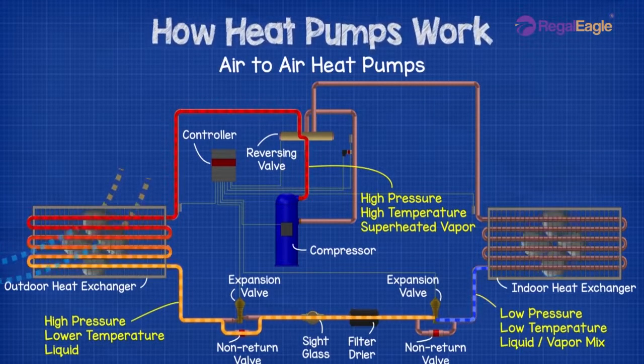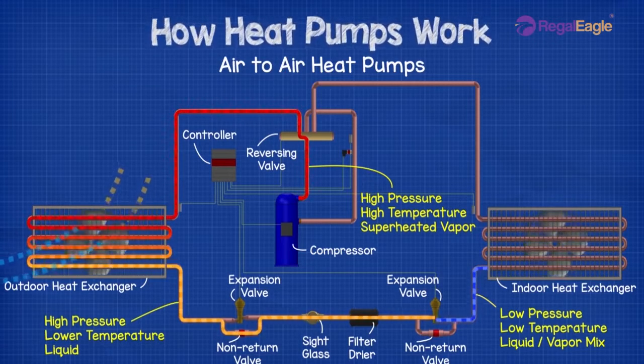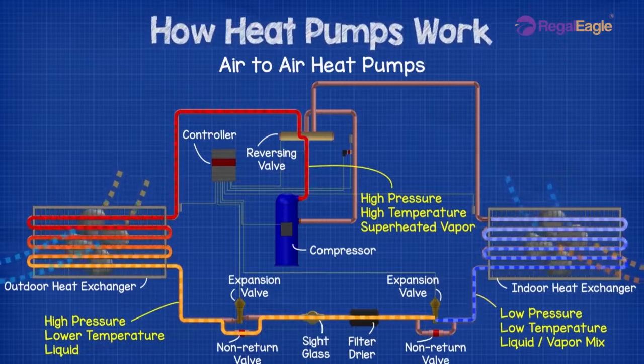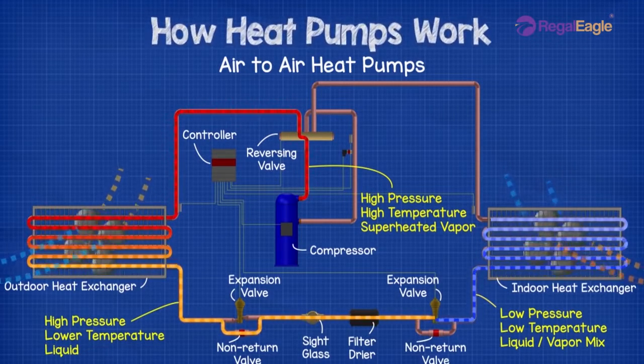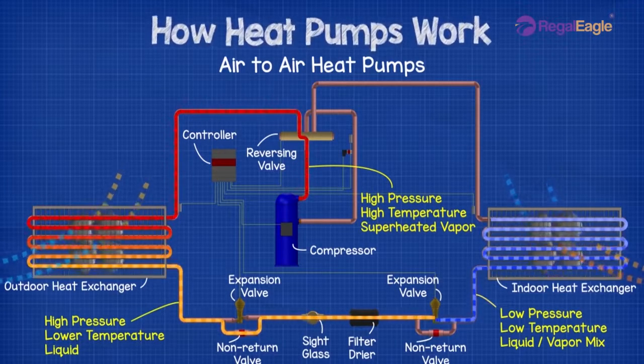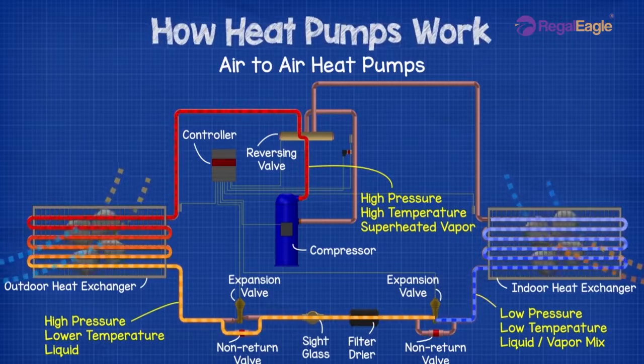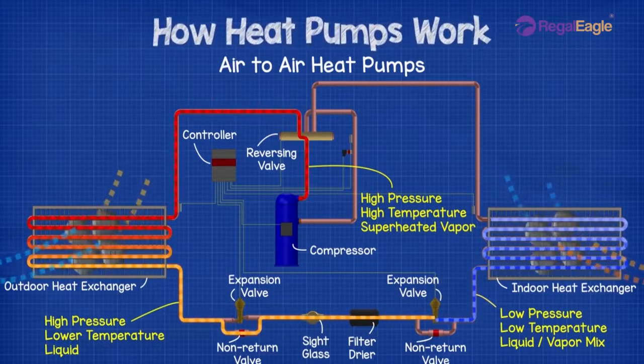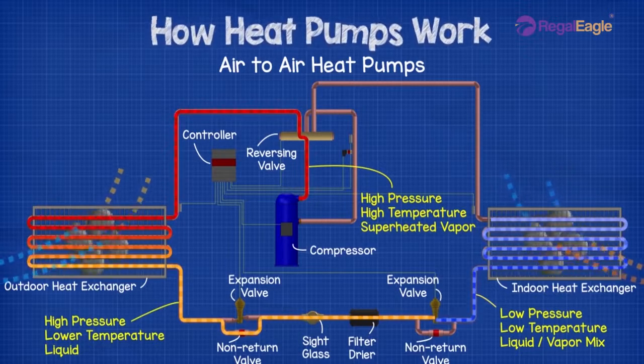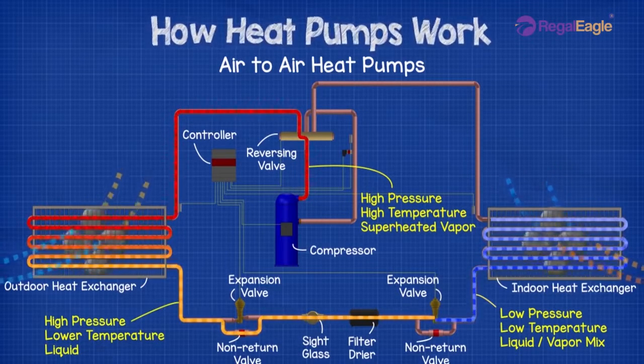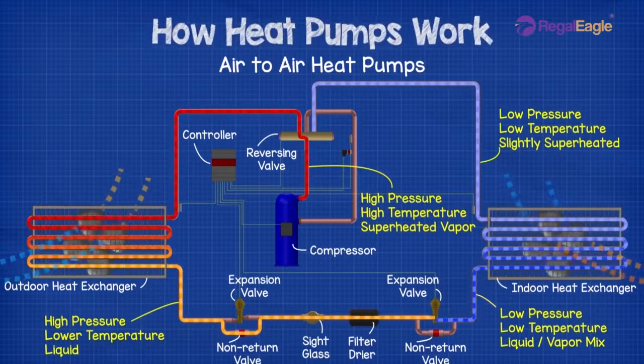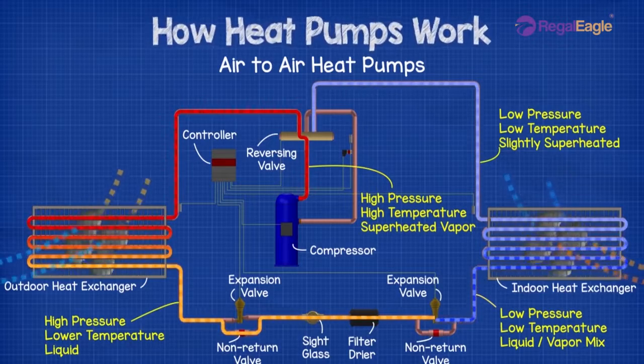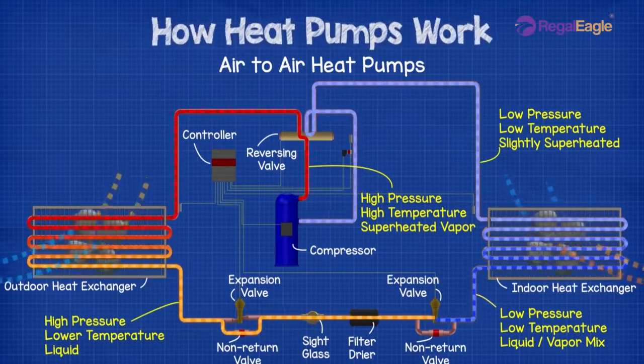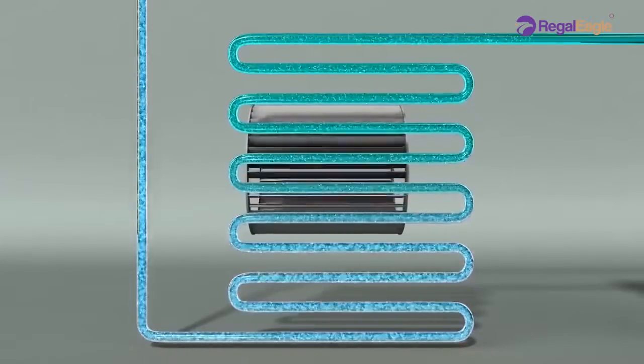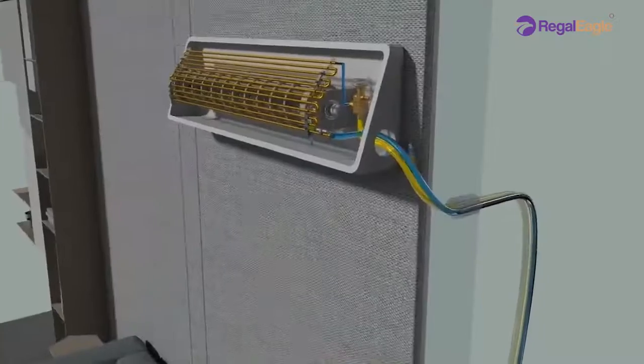It then flows into the indoor heat exchanger, where the fan blows the warm indoor air over the coil, which causes the refrigerant to absorb heat from the air. The air that lost heat becomes cooler, and a cooler breeze comes out from the front of the indoor heat exchanger, circulating round the room. The refrigerant boils and takes the heat away. The refrigerant leaves the indoor heat exchanger in a low pressure, low temperature, slightly superheated state, and flows into the reversing valve, which takes it into the compressor, and the cycle repeats. The indoor heat exchanger can be considered an evaporator, since the refrigerant absorbs the heat in the room, and evaporates to a low pressure, low temperature, superheated state.